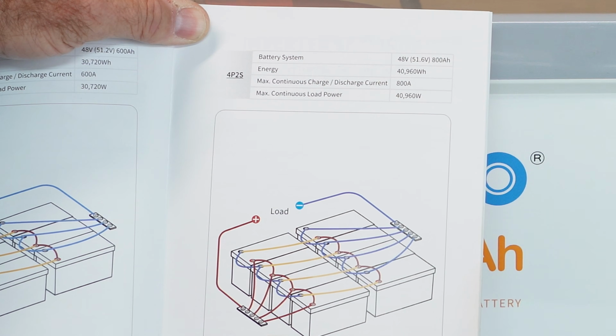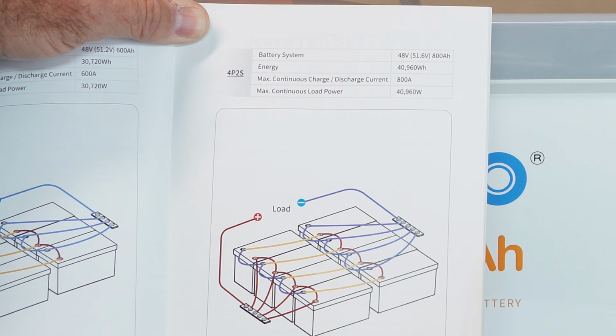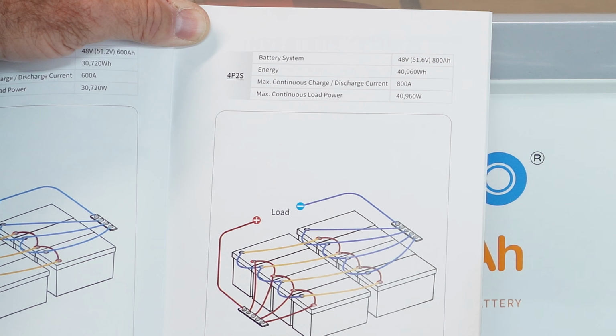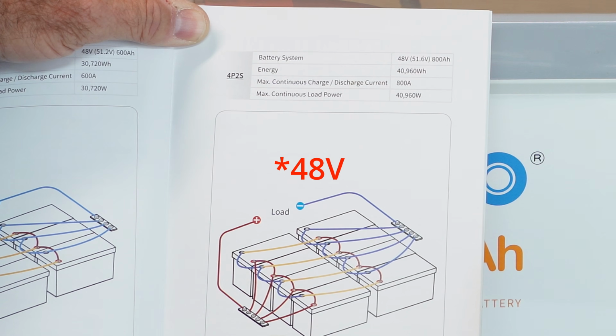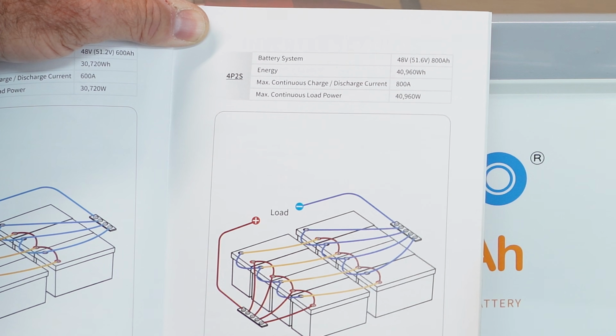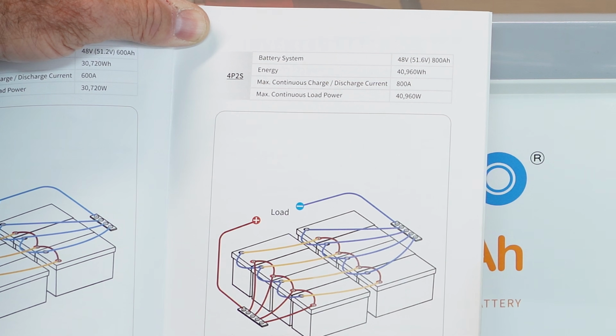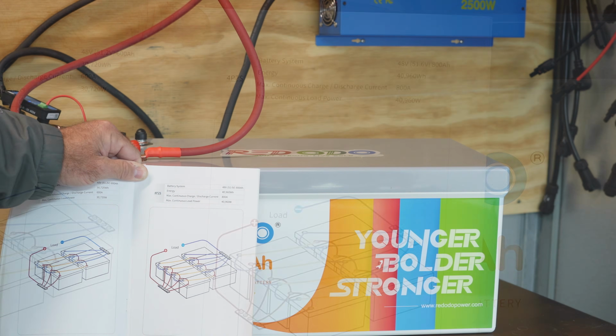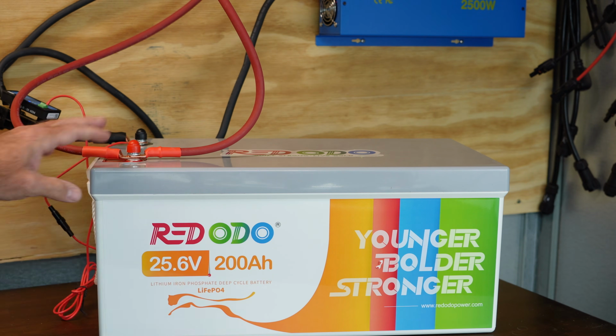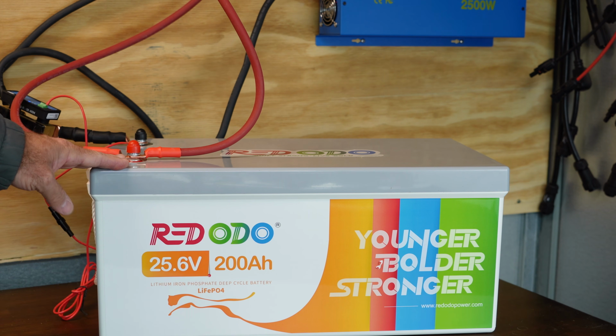And the manual does say you can put this in a 4P2S configuration. That would give you a 48 volt system up to 800 amp hours and nearly 41,000 watt hours, or 41 kilowatts, with an 800 amp max discharge rate. So you could certainly build an off-grid system with this battery.